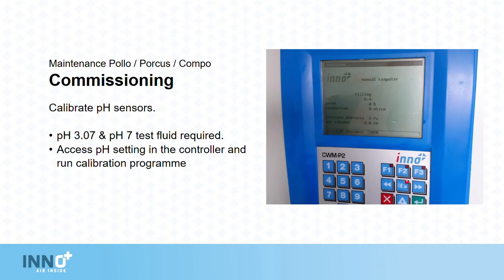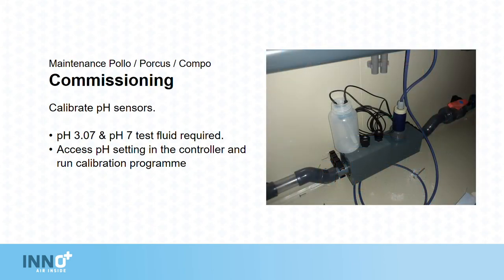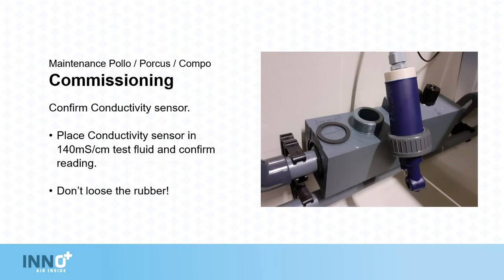Calibrate the pH sensors. pH 3.07 and pH 7 test fluid are required. Access the pH settings in the controller and run the calibration program. This will require immersing the pH sensors in the set fluids as required.